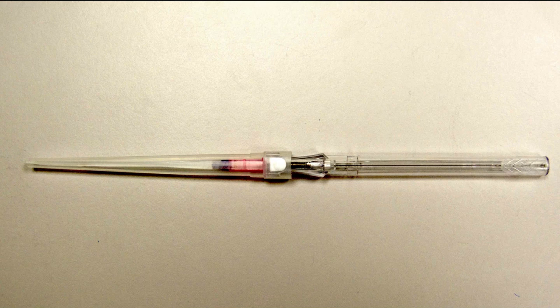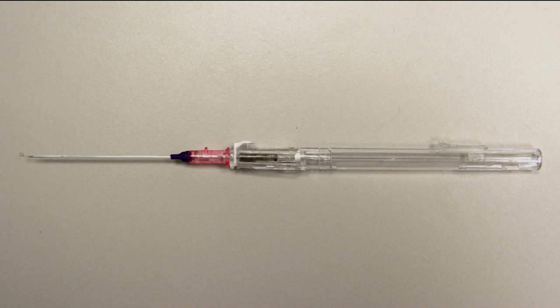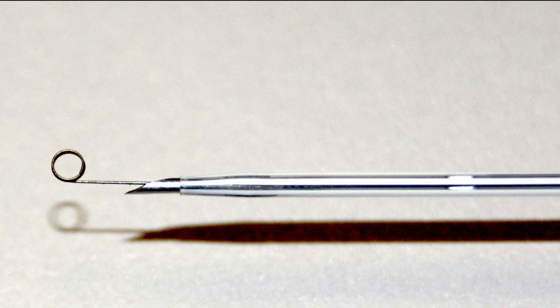This is what the device looks like in its packaging out of the box. When you remove the wrapper, you'll see the device with a plastic cover, which also protects that white actuation button from being activated. Remove the cover, and you'll note that the wire is partially extended. This allows you to inspect the wire before use. The wire is partially extended, so when you take a look at it, you'll notice that nice circular curve of the wire.